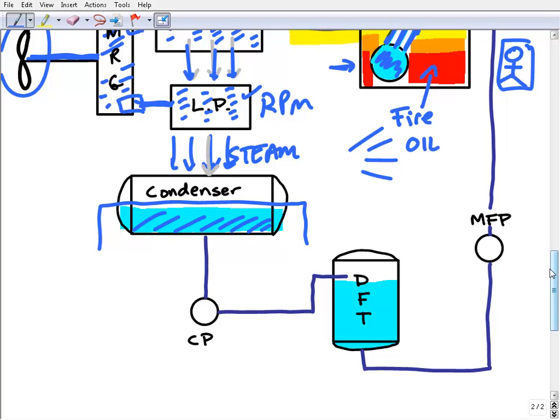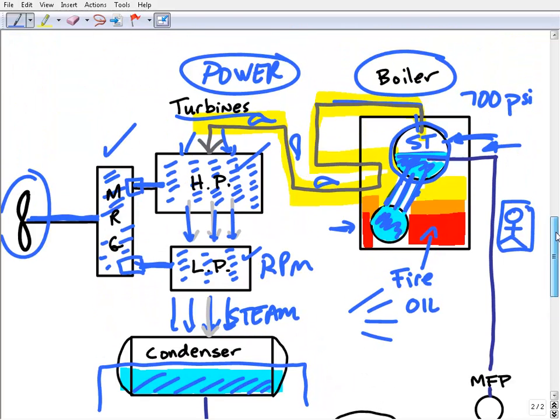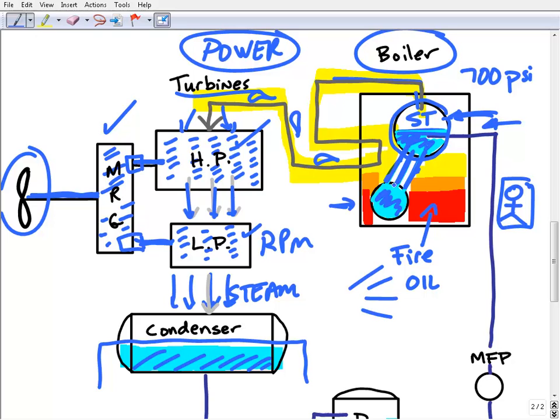You just can't use regular water because you can really, really damage the boiler. Let's suppose I used seawater, or any old run-of-the-mill untreated water, in the steam drum process. What's going to happen is, because you're creating steam, you're going to go through what they call oxidation. You're going to rust out this boiler in a matter of hours.